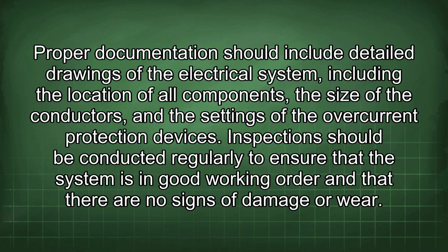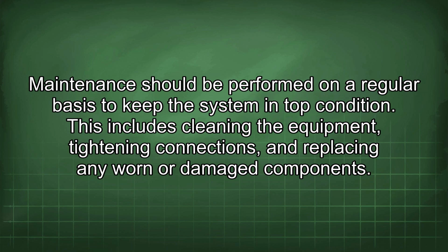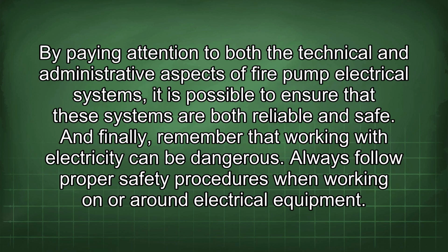Inspections should be conducted regularly to ensure that the system is in good working order and that there are no signs of damage or wear. Maintenance should be performed on a regular basis to keep the system in top condition. This includes cleaning the equipment, tightening connections, and replacing any worn or damaged components. By paying attention to both the technical and administrative aspects of fire pump electrical systems, it is possible to ensure that these systems are both reliable and safe.